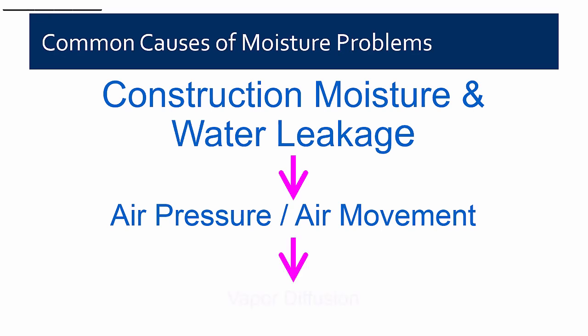We also have potential for problems with vapor diffusion, but in my experience those are really only seen on cold storage facilities and similarly severe cases. Generally, when we talk about vapor barrier versus vapor retarder, in most cases the critical element is not whether it's a vapor barrier or vapor retarder — it's whether it's acting as an air barrier or air retarder.